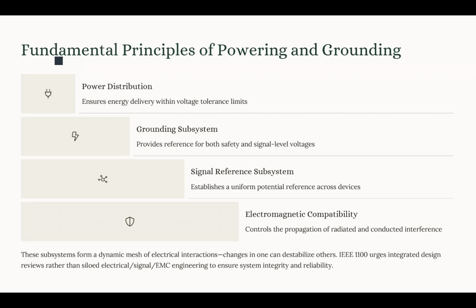Now we have several requirements for that. One is the signal reference grid, which, as we mentioned, is a copper mesh bonded to all the equipment racks, cables, trays, and shields that make sure of signal reference stability. We have a requirement for common mode voltage control, which is the voltage between the neutral and the ground, and it should be, as we mentioned before, less than 1 volt RMS at the equipment input. Okay. Now we have another requirement for this subsystem, which is bonding and shielding, where all the equipment chassis and cables should be bonded to the SRG so they eliminate the potential differences.